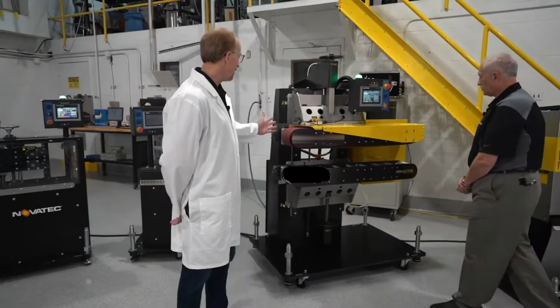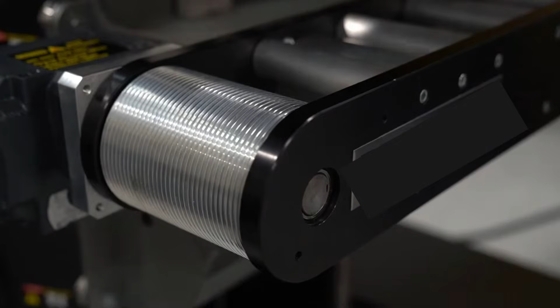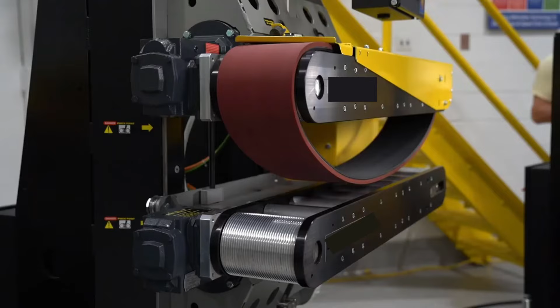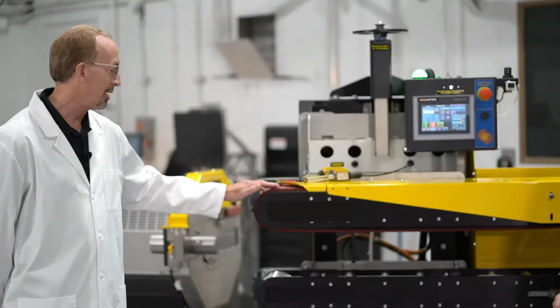With that, we'll go to a one-size larger puller. This particular one is a dual servo, again way too big for making a very small, precise medical tube. We have the poly V belt, same as the other one. We've taken the bottom belt off so you can see the type of belt. Poly V tends to be a thicker belt with a lot of different coverings, but not necessarily the best. It's not very flexible when you're making very small medical tubing, and we'll talk about that further.